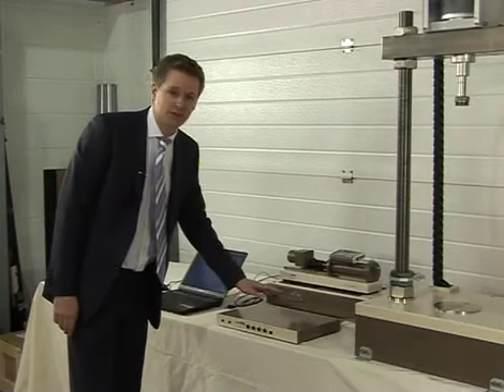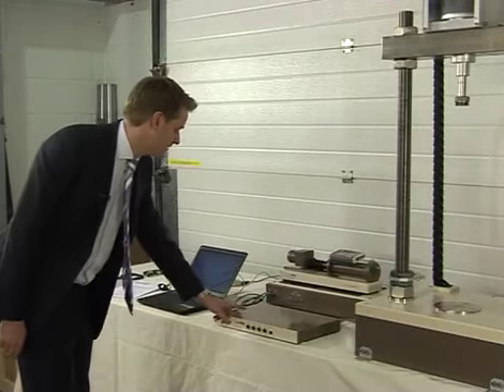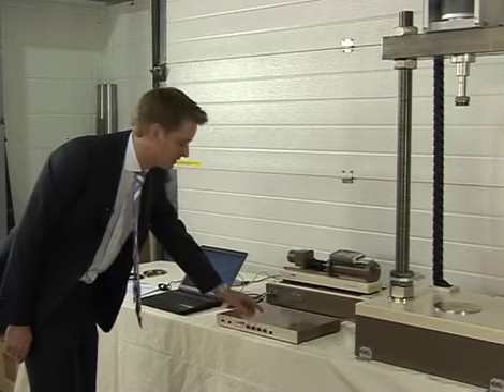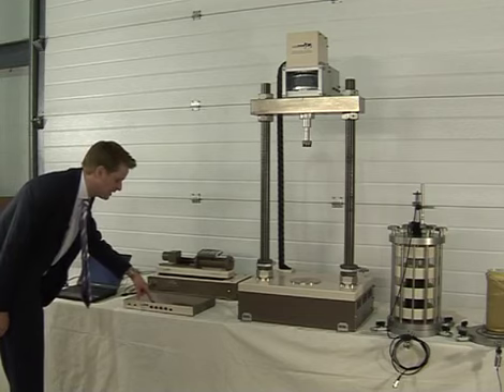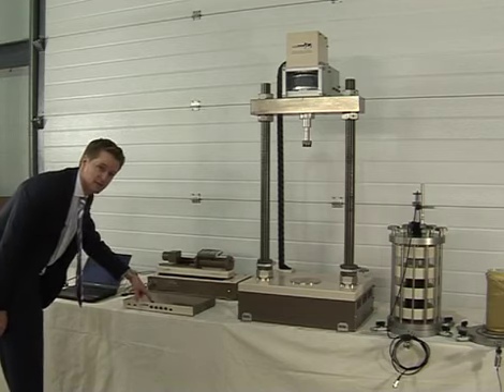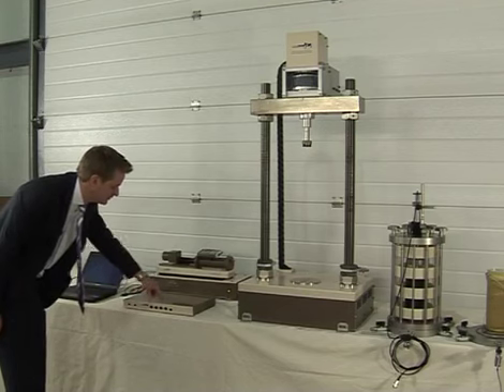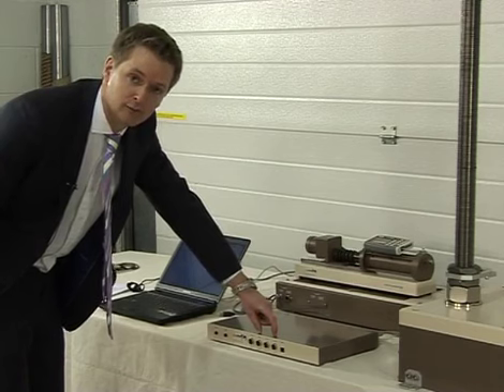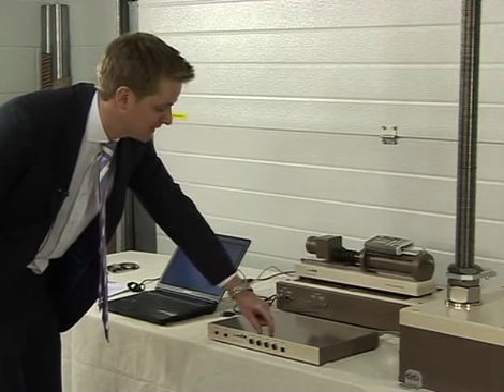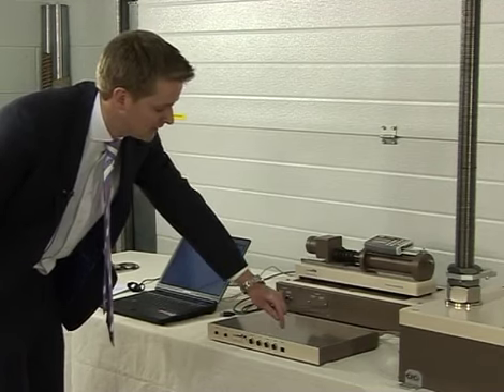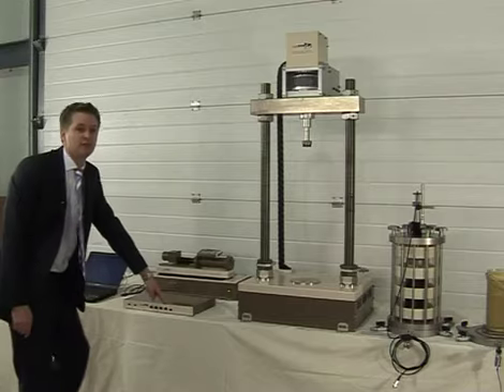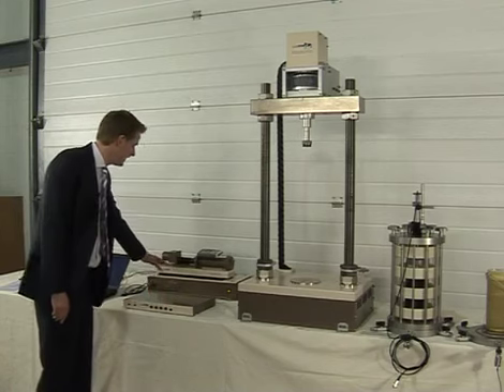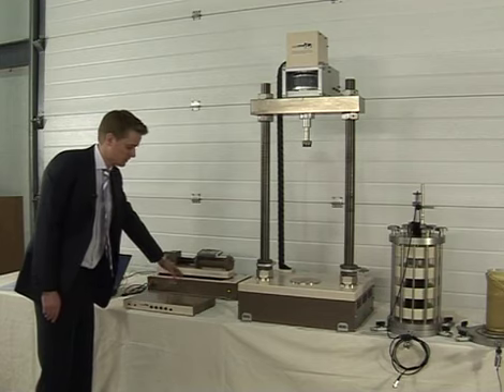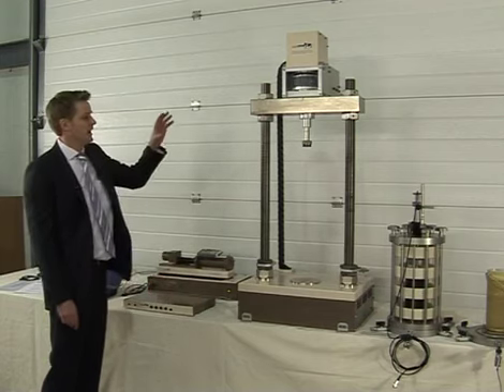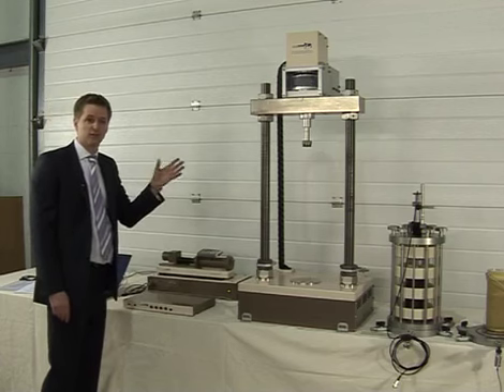Now we're going to connect up the transducers to the DCS unit. Now the channels are dedicated for particular transducers. Channel 0 is for a load cell because it has an input range of plus or minus 30 millivolts. Channel 1 and channel 2 both have an input range of plus or minus 200 millivolts, specifically designed for pressure transducers. Channel 3 has an input range of plus or minus 10 volts, specifically for the output of the pneumatic pressure controller, or alternatively for use with a potentiometric displacement transducer, which commonly has an output of plus or minus 5 or plus or minus 10 volts.